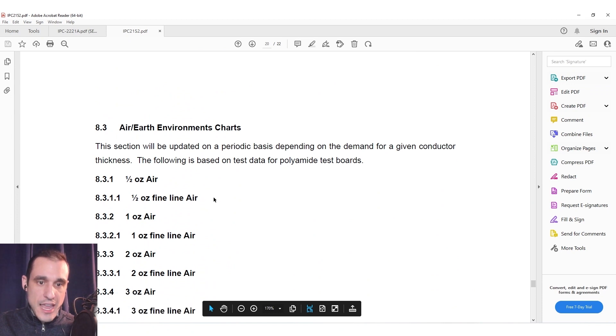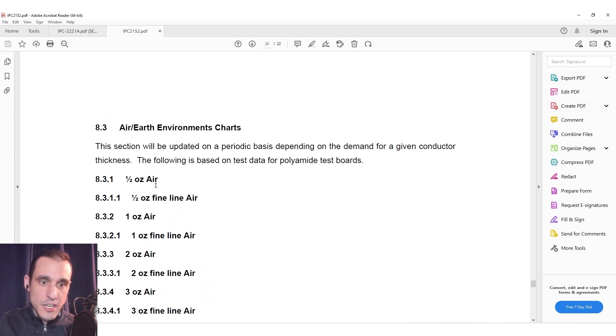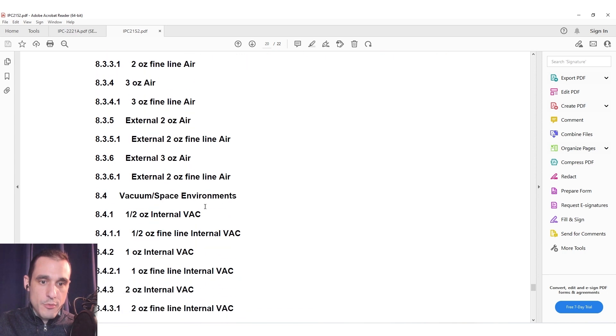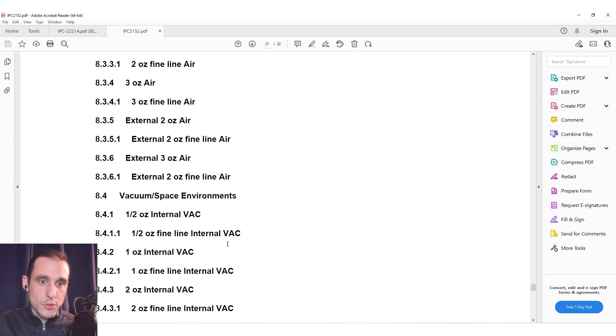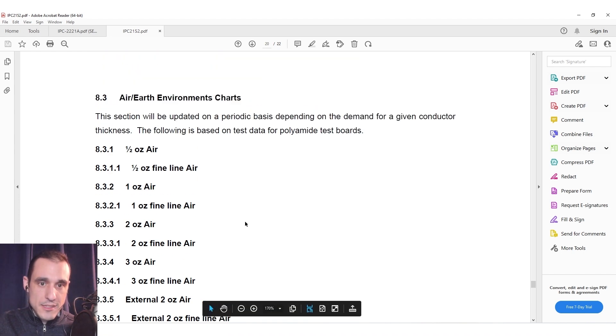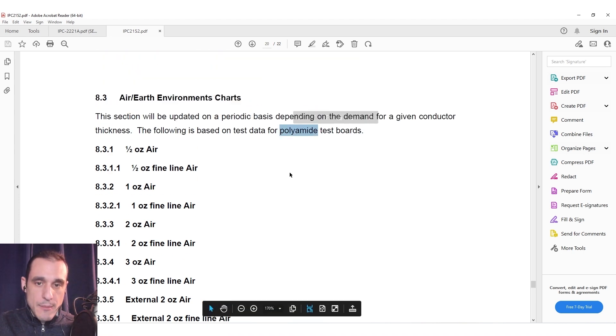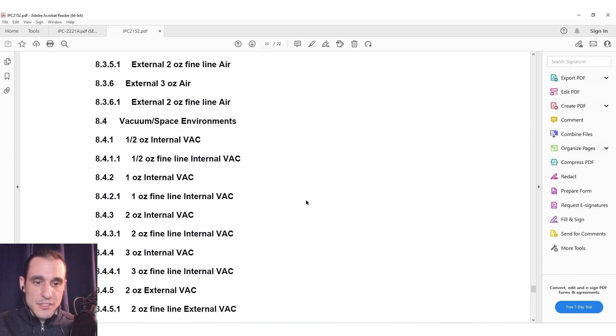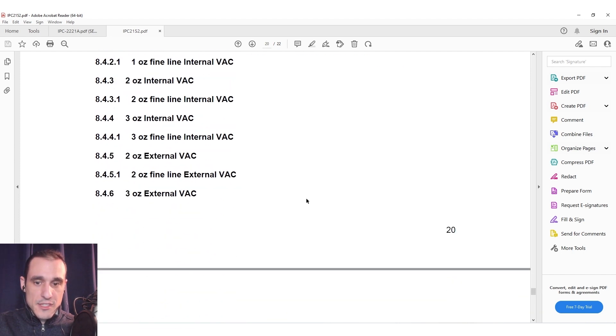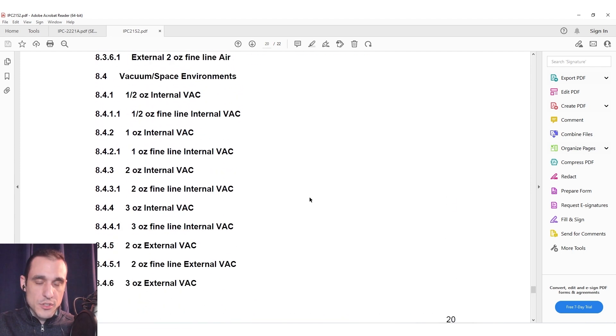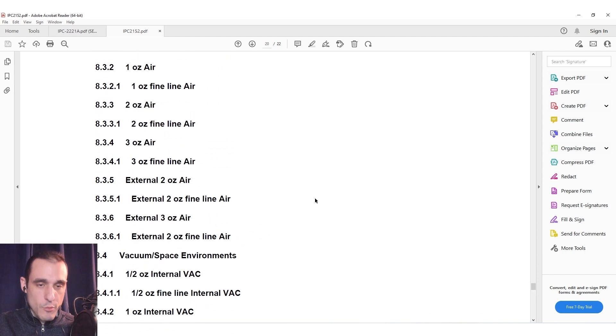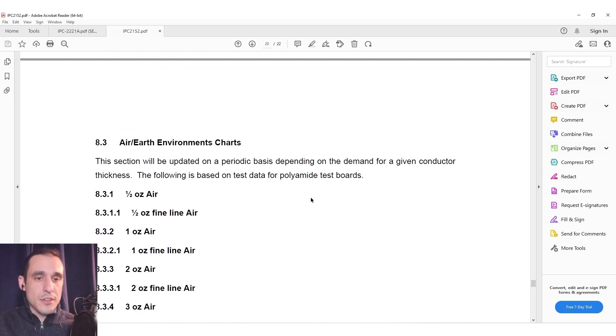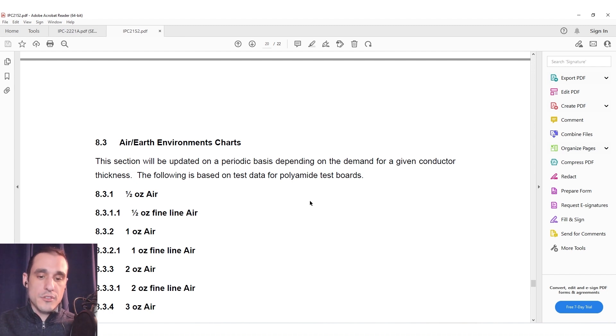So here in section 8 you can see they're even taking account of operation just in air versus operation in vacuum and then of course internal versus external traces several different copper weights and then of course this would be based on polyamide boards but they could do it for other board materials and so this was the intent of 2152 was to gather a lot more data to give a more complete picture of temperature rise in the conductors in a printed circuit board.